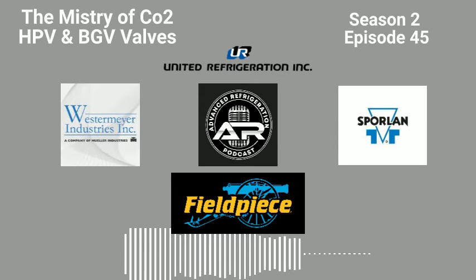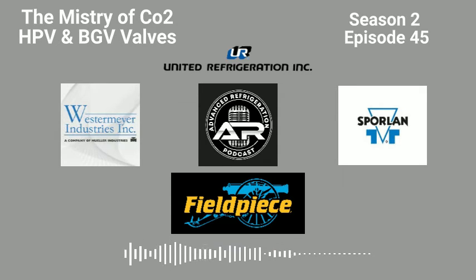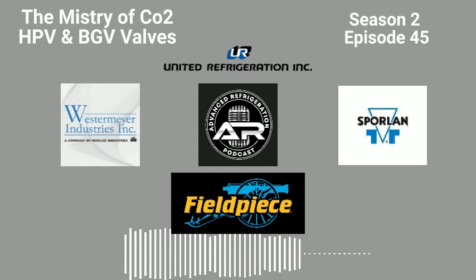And we actually pumped everything down. It was one of those racks that typically has a remote header that has just a ton of gas and liquid lines and all. I got everything pumped down, but main liquid somewhere just said, "Go screw yourself," and kept bleeding. Yeah, that is the worst. You're good, and all of a sudden it's like, oh shit, here it comes. Yeah, you don't know where the hell it came from. It was holding 5 minutes before when you had everything cut open.